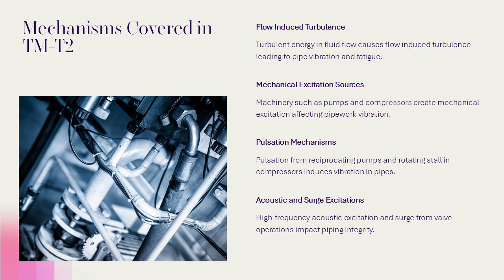Flow-induced turbulence is a common source of vibration in piping systems. The assessment begins by gathering key inputs: external pipe diameter, D_xt, wall thickness, T, maximum span length between supports, L_span, and support type classification, stiff, medium, or flexible. Fluid properties such as velocity, V, density, ρ, and gas dynamic viscosity, μ_gas, are also required. For flexible systems, structural natural frequency, F_n, may be considered in advanced screening.